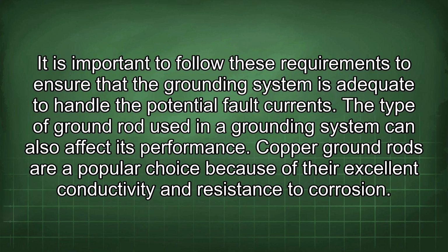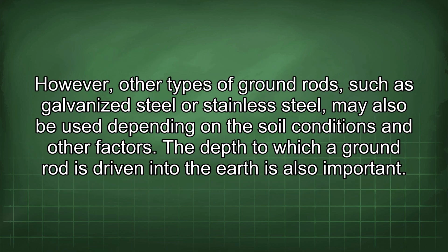The type of ground rod used in a grounding system can also affect its performance. Copper ground rods are a popular choice because of their excellent conductivity and resistance to corrosion. However, other types of ground rods, such as galvanized steel or stainless steel, may also be used depending on the soil conditions and other factors.